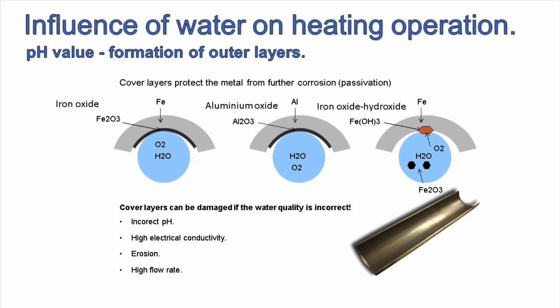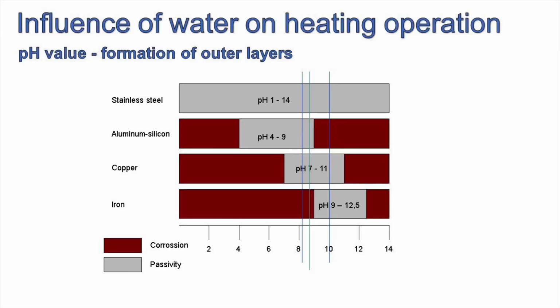We also tested the pH of the water within our system. The reason we do that is that metals can create their own covering, called oxide layers. These oxide layers allow the metals to protect themselves, giving a very thin coating on top of the metal. It's essentially like an inhibitor, a natural layer of protection. Different metals have different ideal pHs. For heating systems, typically we say about 8.5, because that allows for aluminium as well. With aluminium systems, you don't really want a pH above 9, but above 9 is quite good for stainless steel, iron and copper, etc. So as long as the pH is around 8.5 or above, we know our metals are going to protect themselves within the system.